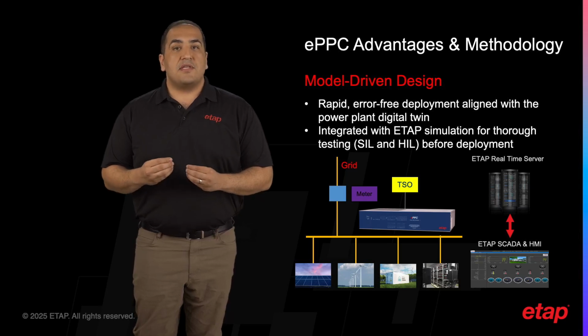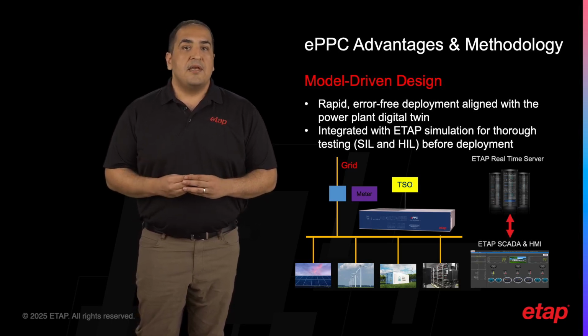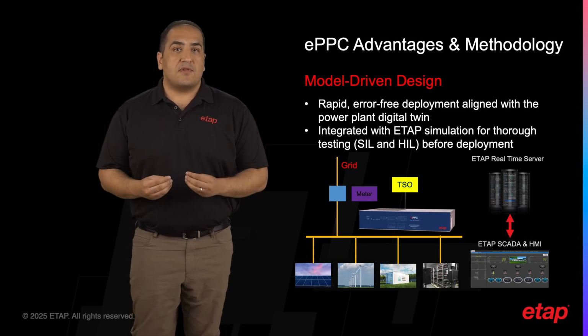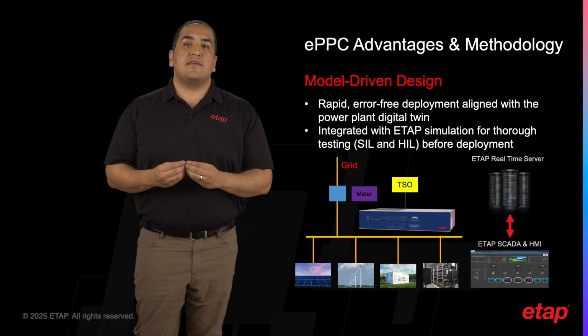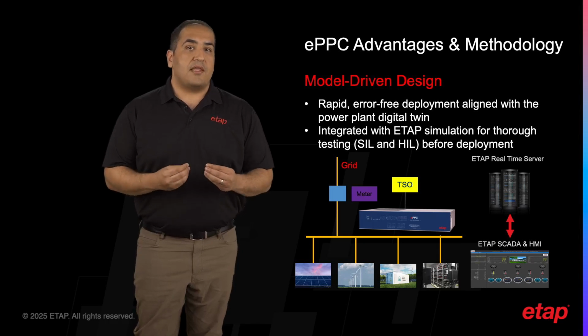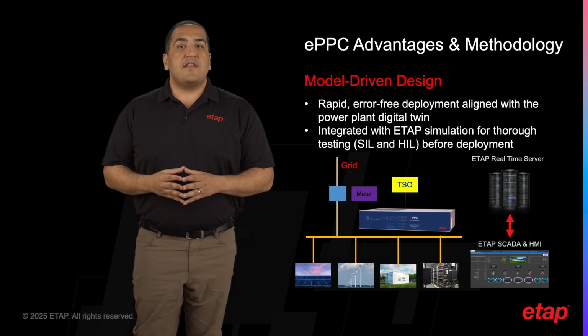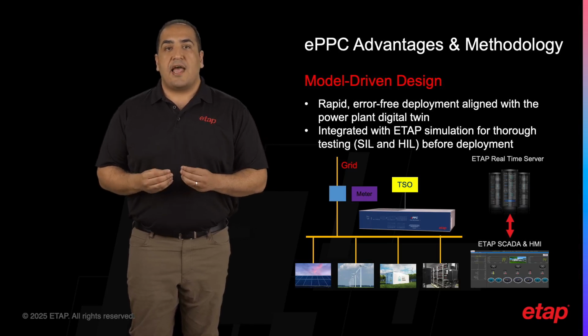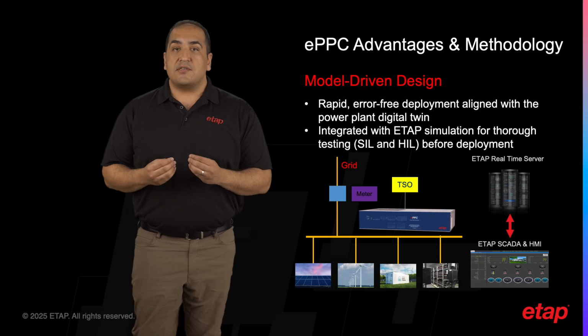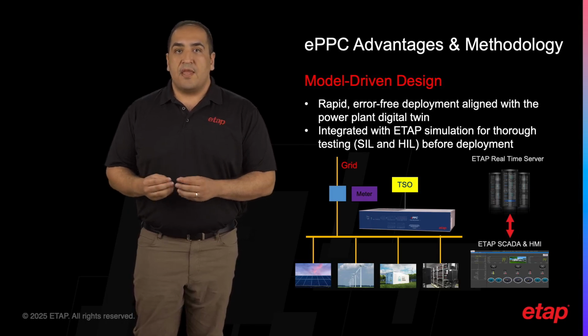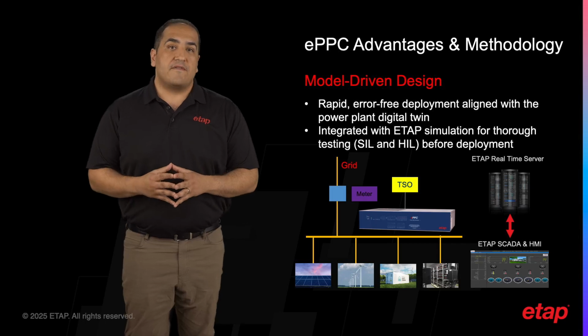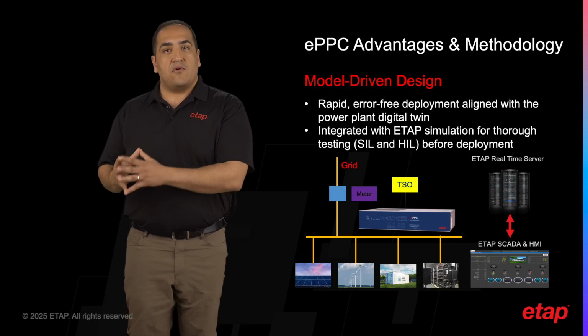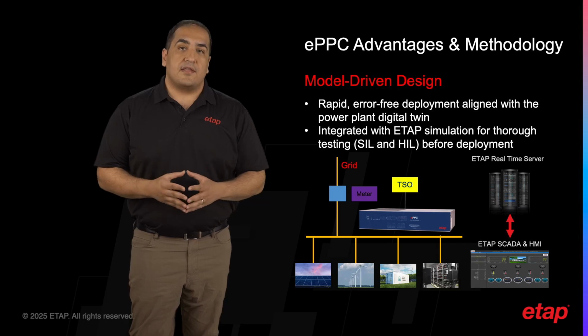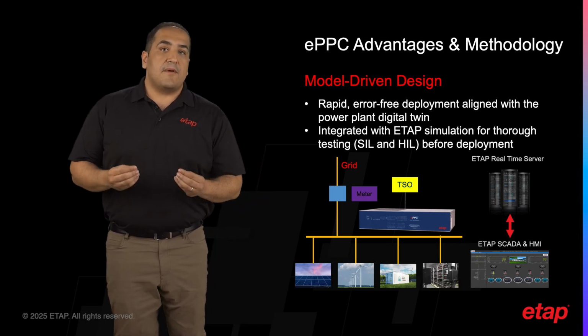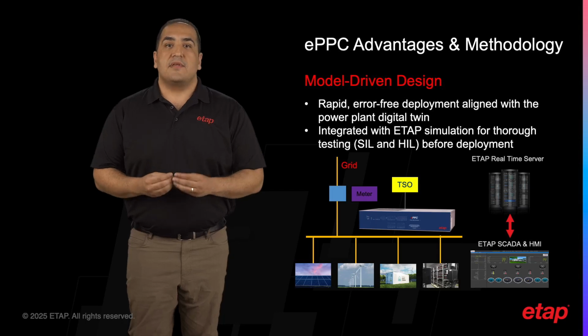By closely integrating with ETAP's robust simulation environment, ePPC allows for thorough testing in both software-in-the-loop and hardware-in-the-loop configurations before any real-world deployment. This level of testing and validation significantly enhances reliability and helps avoid costly errors once the system is live. Additionally, ETAP simulation software offers critical study types like grid code compliance studies and transient stability analysis, which complement ePPC's capability and ensure that the entire system is well prepared for operational challenges.